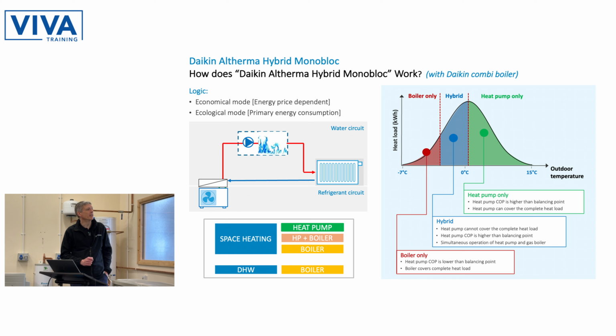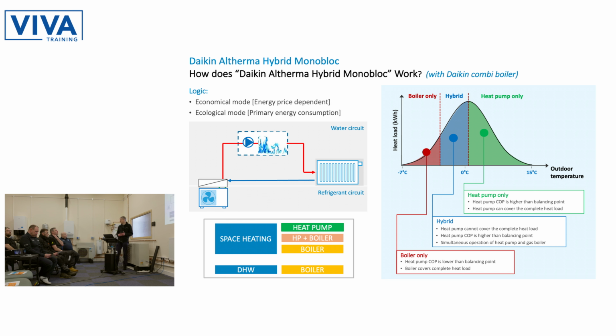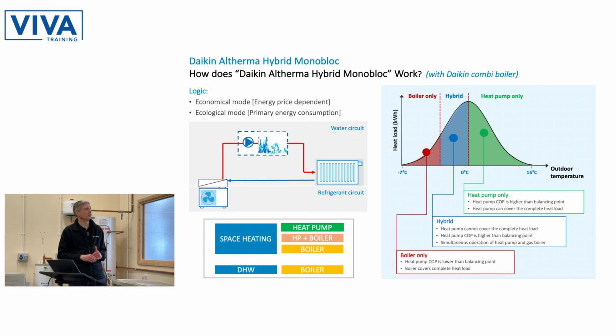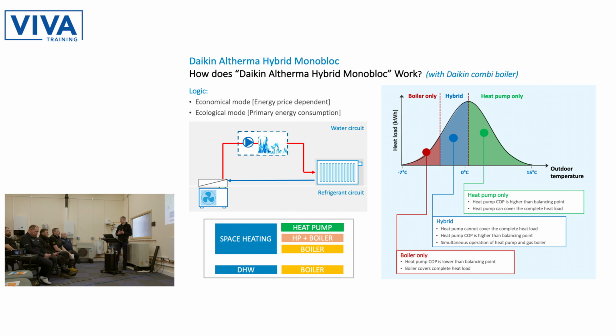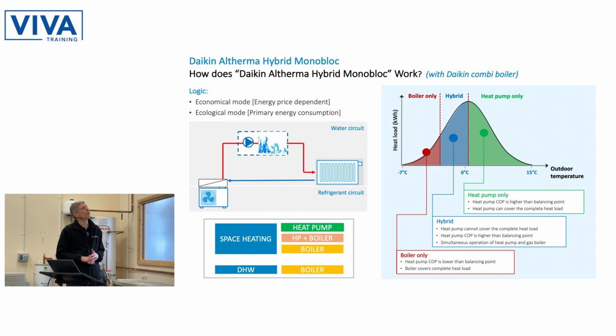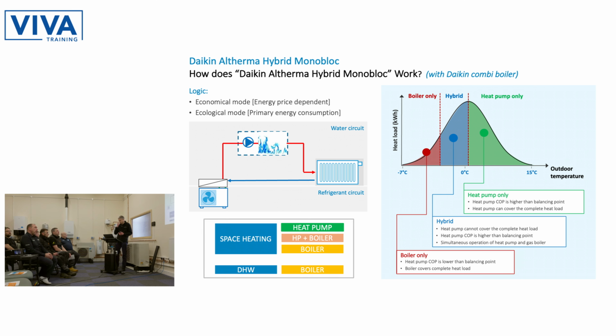So what's the logic behind this in terms of how it decides what it's going to operate at any given time? You can actually program two different modes into this system. Economical mode, which is based on energy prices, or ecological mode, where it's dependent on carbon factors, so that's the amount of CO2 emitted for gas or electricity. And you can program these into the user interface, so you can tell it what the user is paying for their electricity or gas. We're expecting 90% of installations to probably focus on the economical mode. At the moment, there's only one tariff that you can put into it, but that's something we're working on, and we need to combine it with scheduling to look at that.